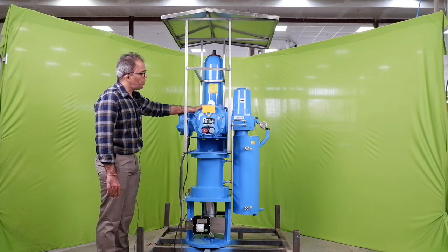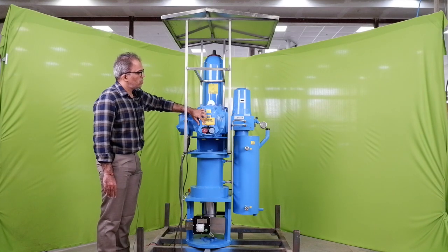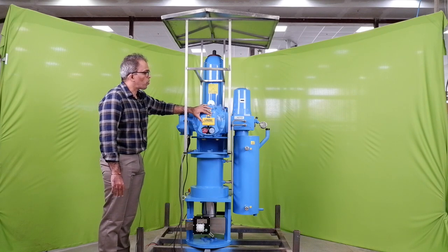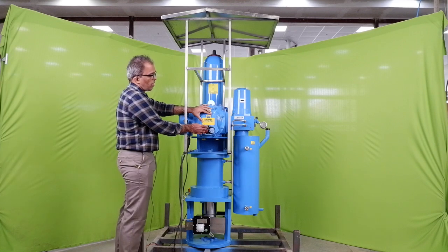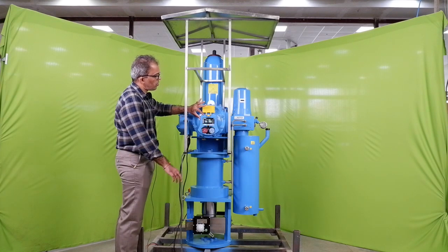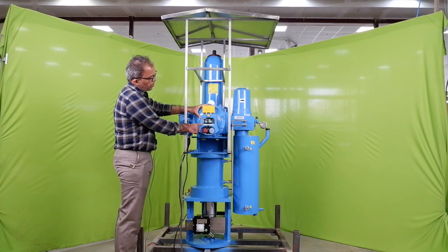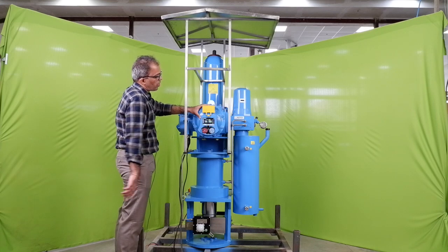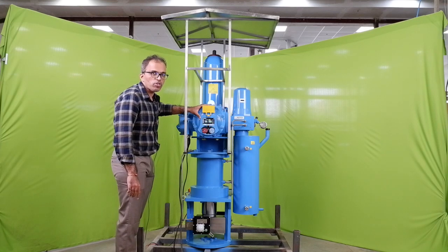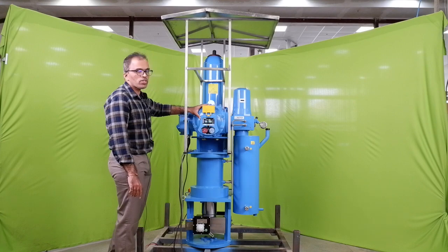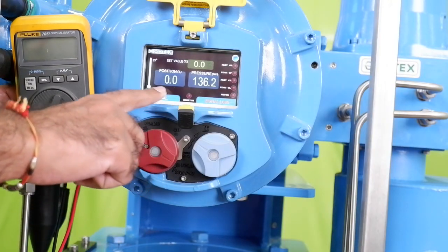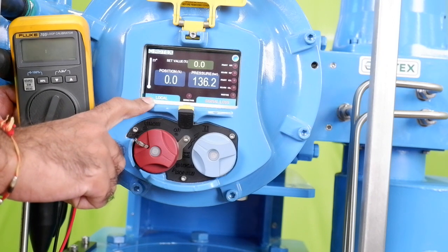The electro-hydraulic head has an LCD display which has a cover to protect from UV rays. The electro-hydraulic display shows the position of the valve, the accumulator pressure value and the set point value. It also shows the condition of all the proportional valves, different alarms and different modes. Here the display shows that we are in the local mode.